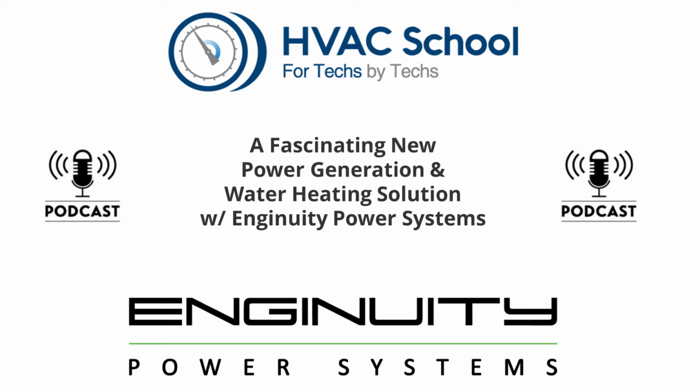Awesome. From a base standpoint, what's going on is you have an engine that is a generator, and you're taking all of that traditionally wasted heat from the exhaust, and the engine heat it creates through friction and vibration, and you're recovering all of that into the water. And if for whatever reason that doesn't create enough heat, there is a backup electrical element that's powered by the energy being produced by the engine. Is that correct? Yeah, you're exactly right. So that gives a lot of flexibility to the engine.